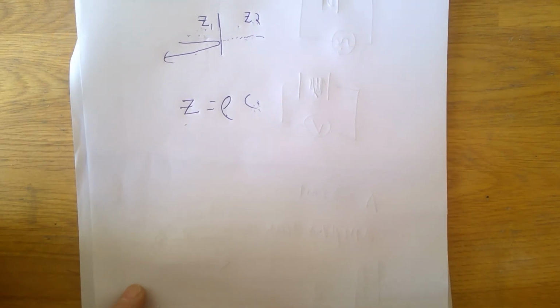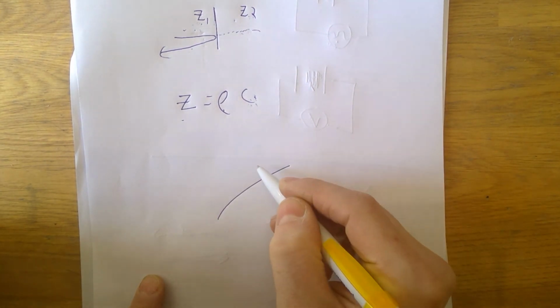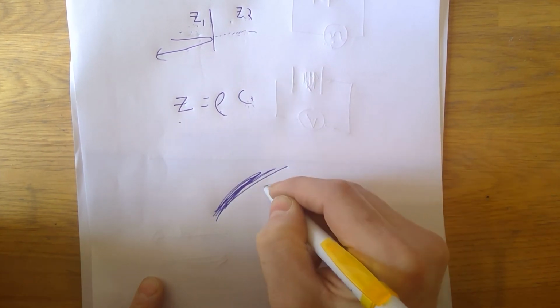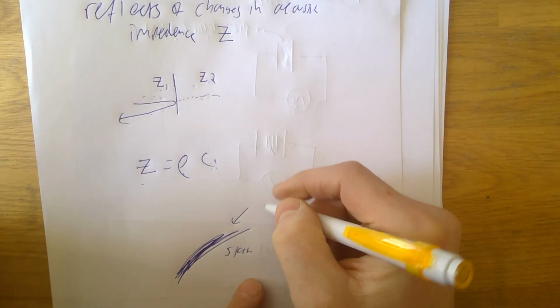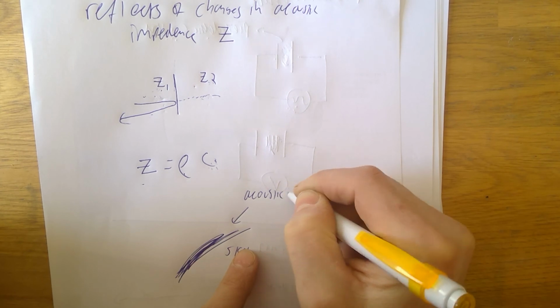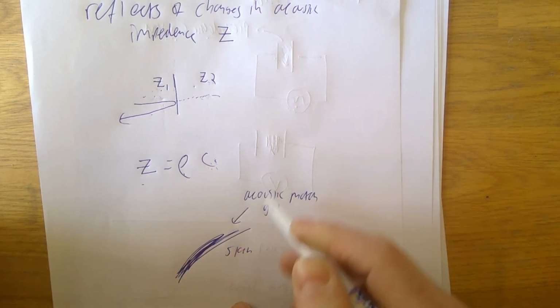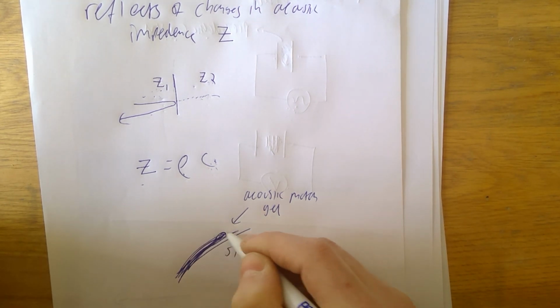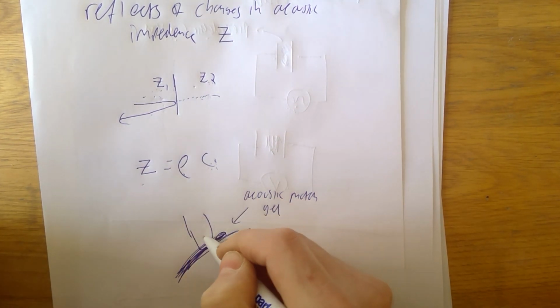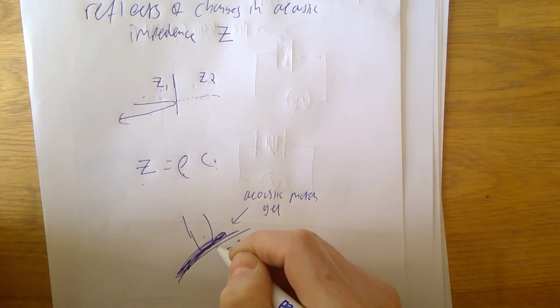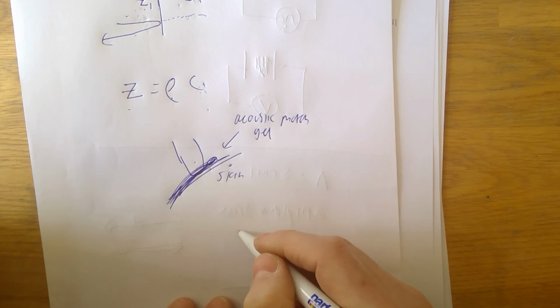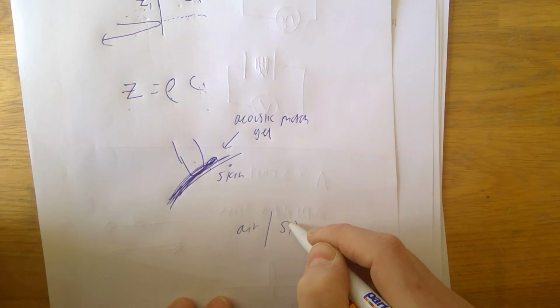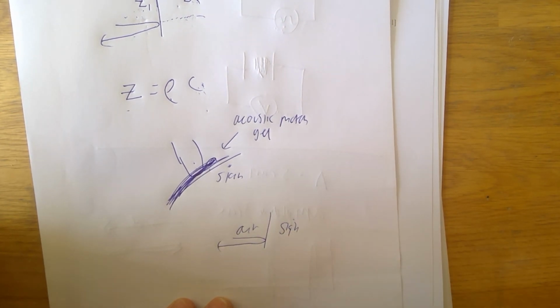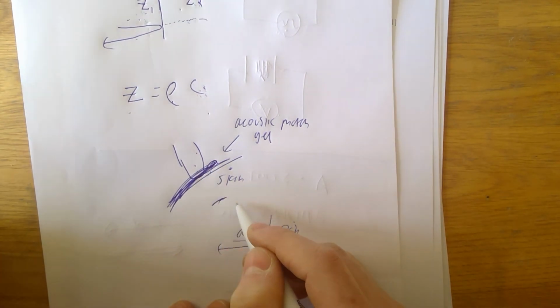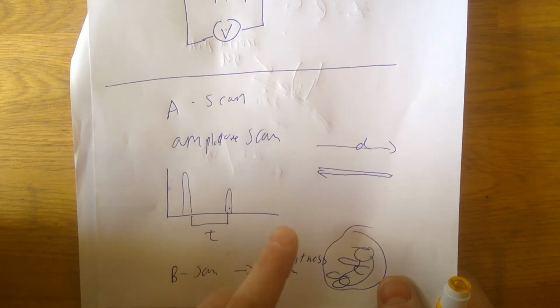That's why when somebody does go for an ultrasound scan, they get really slathered up with gel on their skin. And that's what we would call acoustic matching gel. It matches the acoustic impedance of the gel to the skin. So when you bung your ultrasound probe on, there isn't loads of ultrasound reflected straight off the surface of the body. Without the gel, you'd be going from air to skin, and almost all of the ultrasound would be reflected. No good. We want it to go in the body so it can then reflect off things inside the body and come back, and then we can work out where those things are in the body.